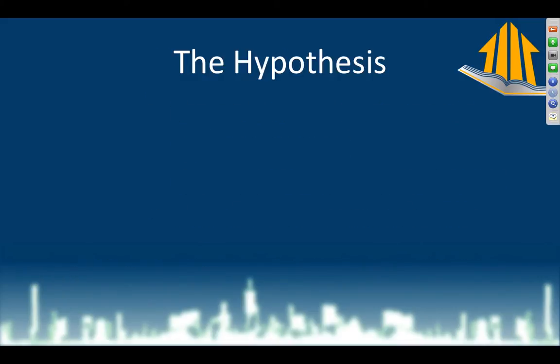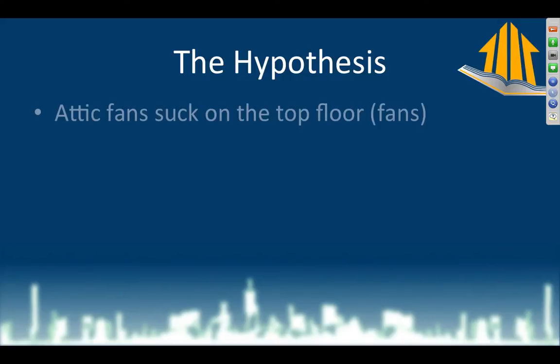So here is my idea. Now that I've got all this raw data about what's going on in this house, the attic fans are sucking on the top floor, right? Because they're sucking on the attic, and the attic is sucking on the top floor because we know we have top plate leakage, which I took a picture of with my infrared camera and also measured with a pressure pan, and did zonal pressure testing on the attic.